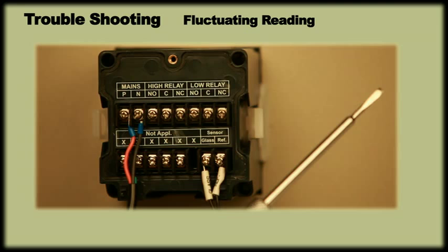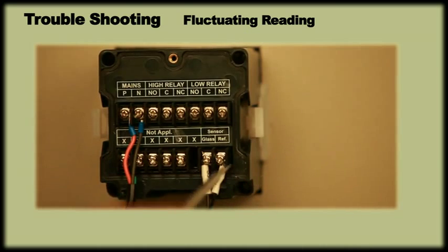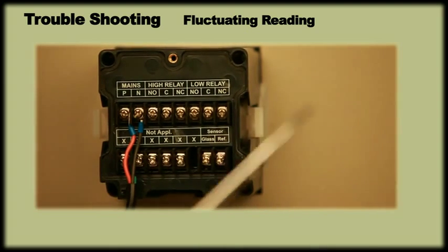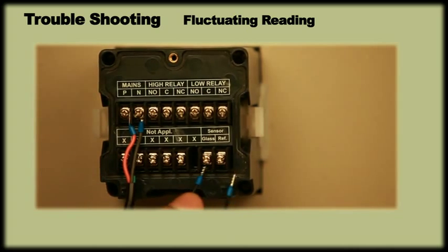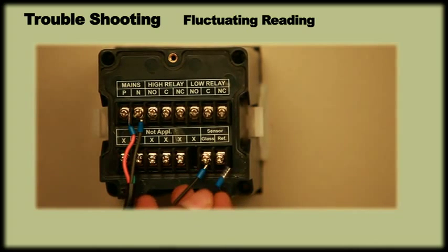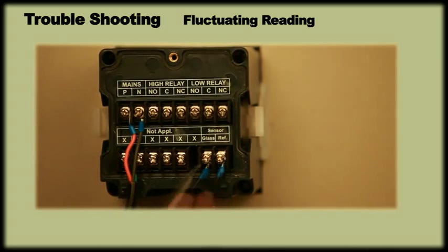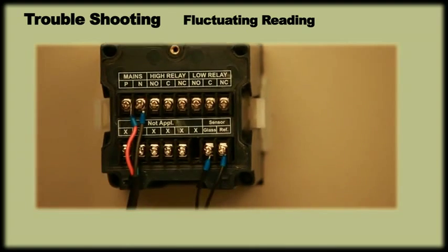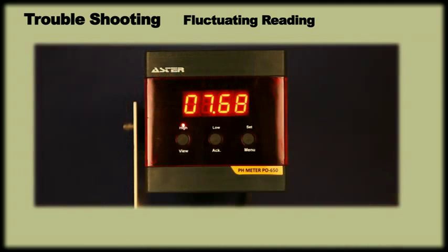It could also be because the sensor is not able to send signal to the meter. In that case, disconnect the sensor from the meter by removing the wires and short sensor input terminals. Check the reading. If the reading is around 7, then contact the nearest service center.